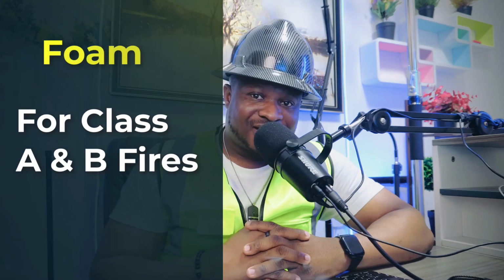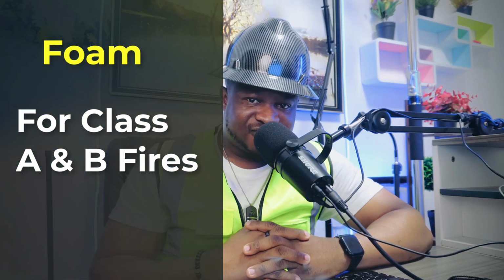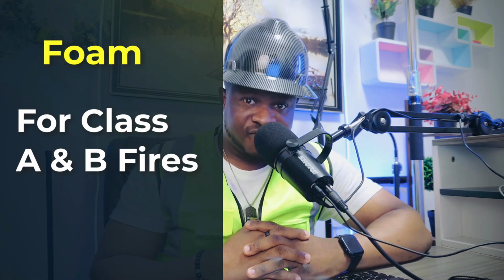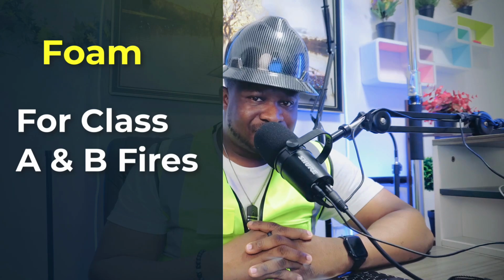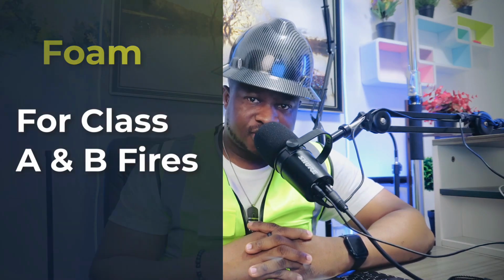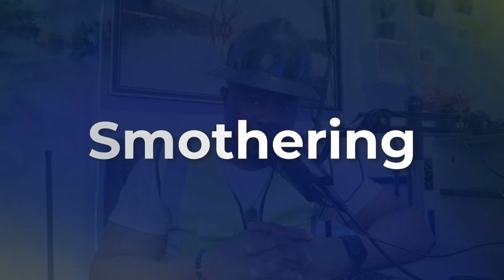Foam is suitable for Class A and B fires, that is fires involving ordinary combustibles and flammable liquids. The foam creates a barrier between the fuel and the oxygen, thereby suffocating the fire of oxygen while starving the fuel. The process of suffocating or depriving the fire of oxygen is called smothering, and the process of sealing the fuel is called starving.